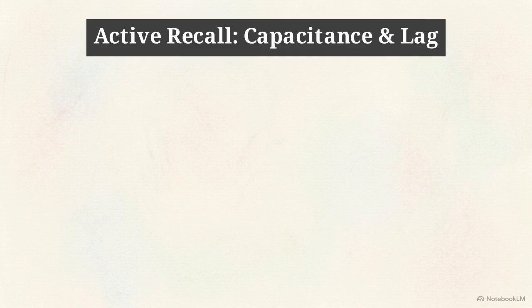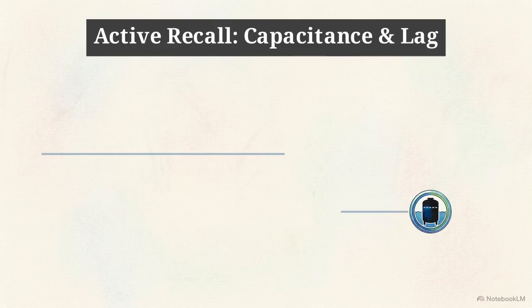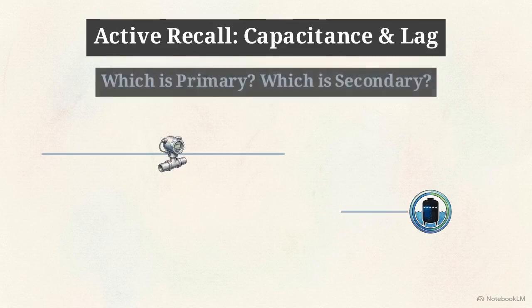Here is a P&ID for a distillation column reboiler. We have a bottom liquid level sensor and a steam flow sensor. Take 5 seconds. Which one is the primary PV and which is the secondary? Remember the rules of capacitance and lag.